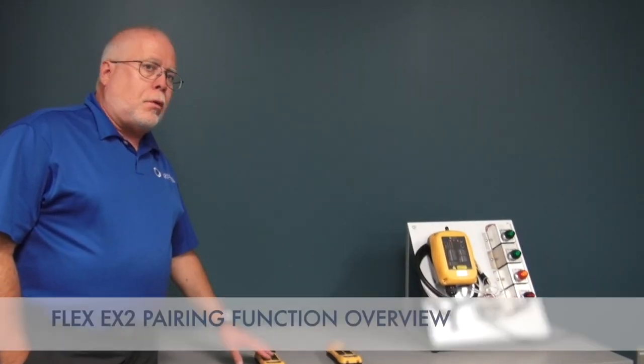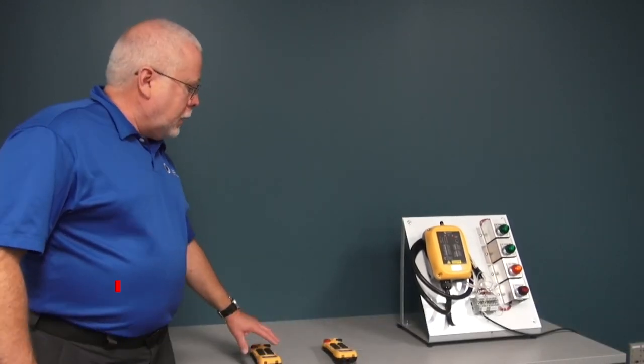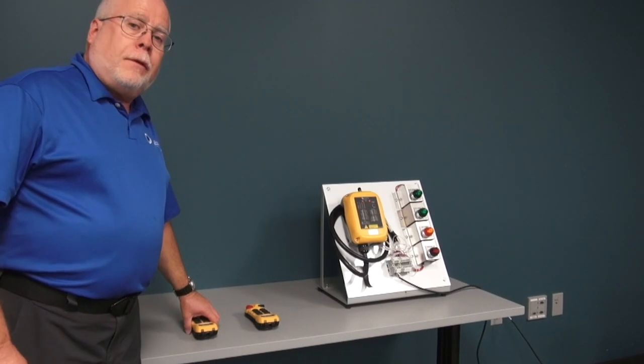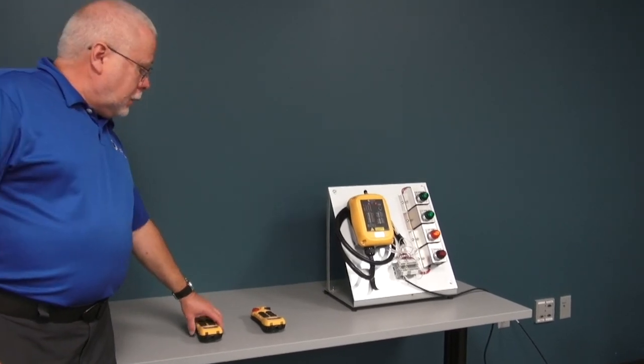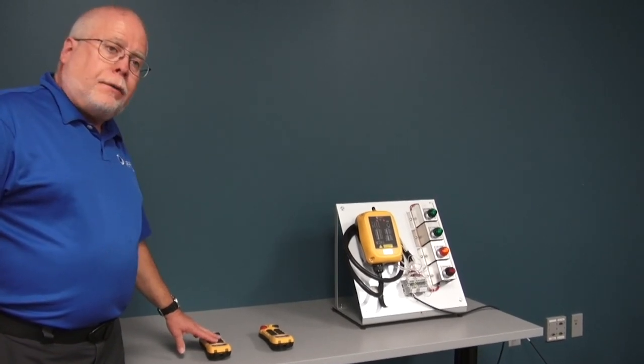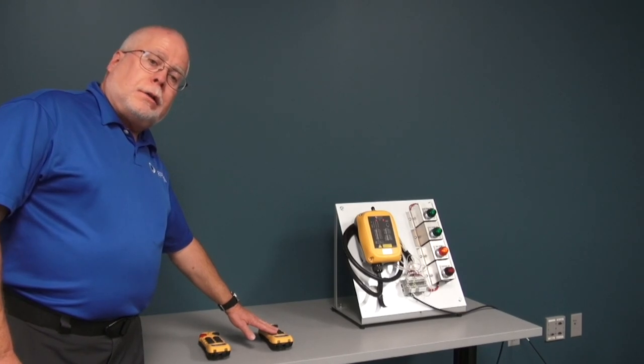The Flex EX2 product allows us to do what's called a pairing function between two different transmitters or from a receiver to a transmitter. This is all through RF communication, and when we do the pairing function between transmitters, one transmitter sends RF information regarding its programming to a new transmitter.